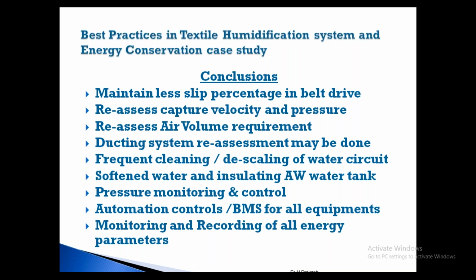Then descaling, this maintenance. The spray pipe, there will be a 40 mm pipe. If you see, there will be 10 mm of scaling. They don't do the maintenance. They will tell there is no time for maintenance. You have a spare set, and you do it in the third shift, that is early morning, at night 1 o'clock they can start replacing the pipes. That they should do. Like that, if they replace, then descaling is to be done, soft water and insulating the water tank.